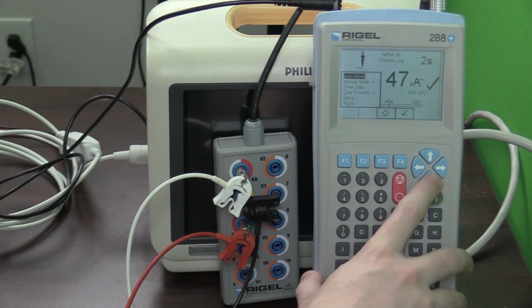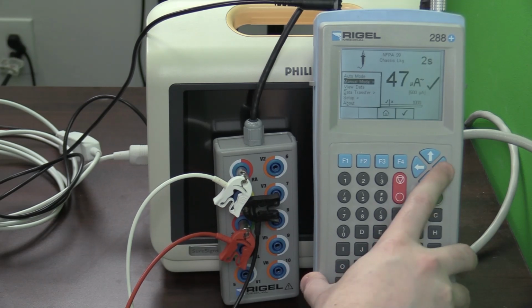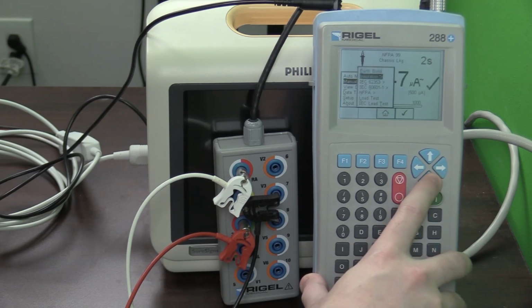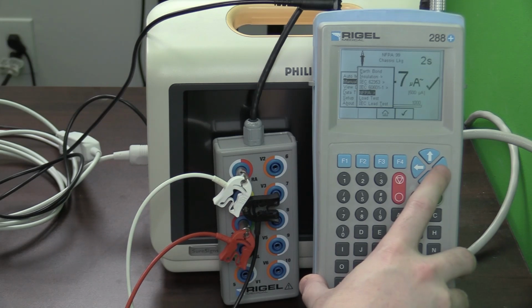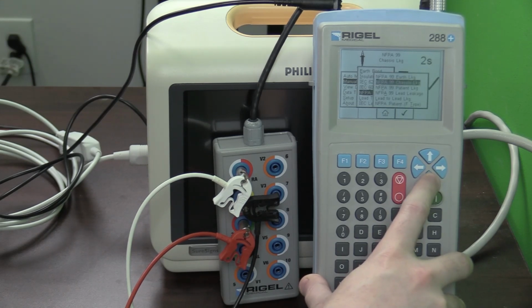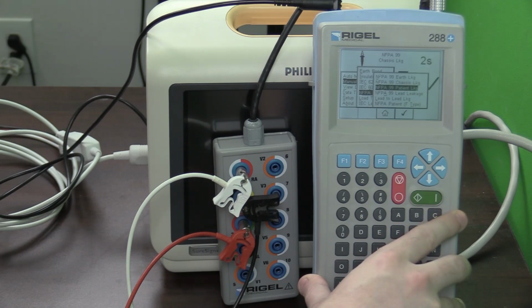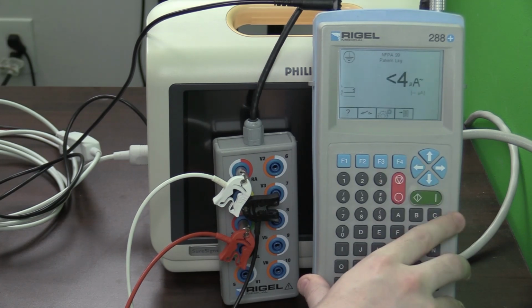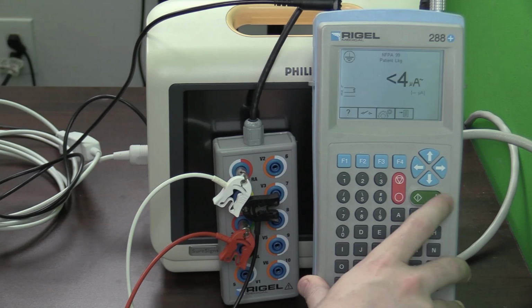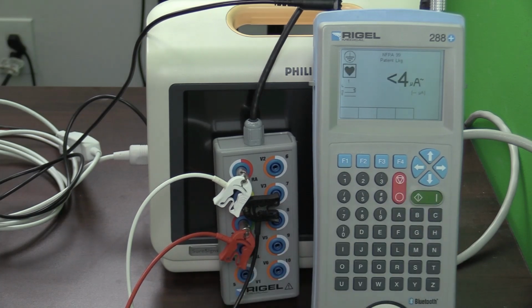Select F4 to open up the menu, go down to manual, and we are still testing for NFPA standards. So go down to NFPA, and this time we are testing patient leakage. Scroll down to patient leakage and select F4 to select your test, and the green button to start your test.